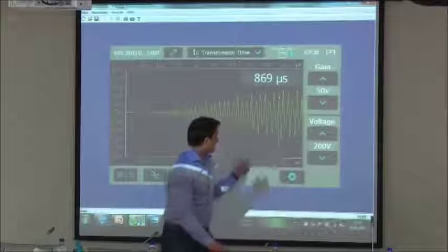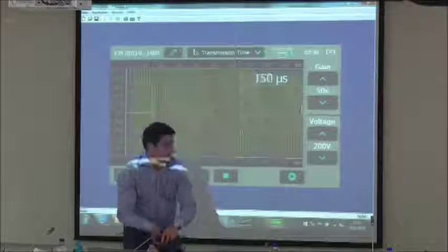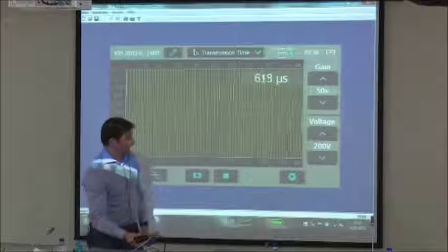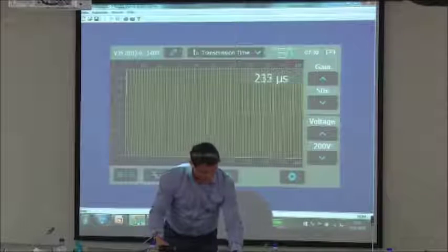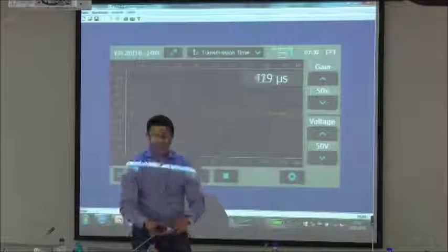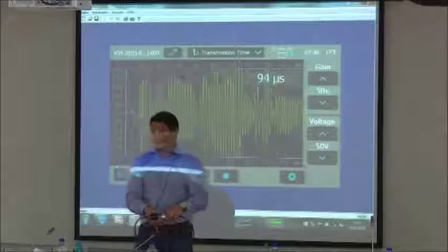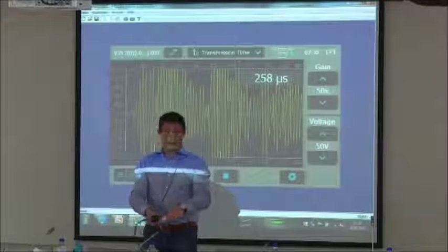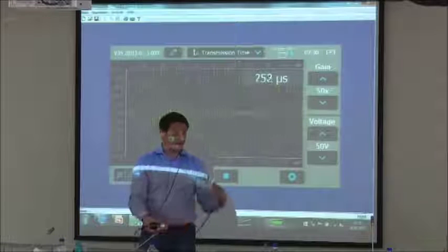So that you also see how it works. If I use the transducers, you can see it's too high because it's closed. Then you have a calibration, and this calibration is only for, let's say, in-house. Before I go to construction site, I use this.